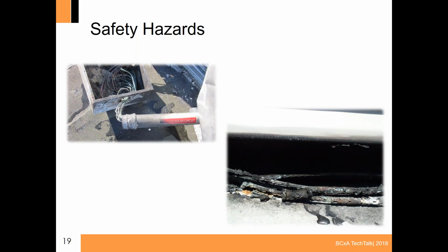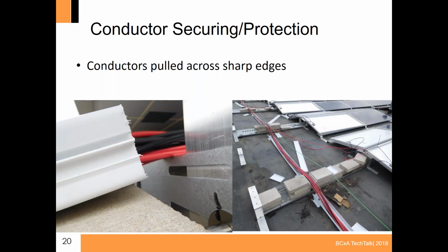We'll touch upon a few different safety hazards now that we've encountered. First and foremost, and in my mind one of the easiest to avoid, is conductor protection. We've got live DC conductors all over the roof, all over the array. In most cases today, these systems are operating at about 1,000 volts DC, or they're designed for 1,000 volts, maybe operating around 800 or 900 volts. We want to make sure these conductors are properly protected. In this case, it was a very poor raceway choice, raceway design, and we can see that these conductors are directly against the sharp edges of the racking. So it's super important to consider the external effects on these conductors, making sure that they're properly protected from physical damage or abrasion.